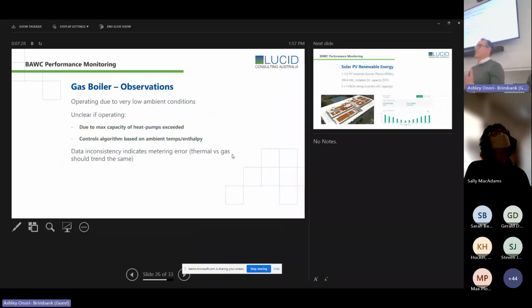So at this stage, we're still working through it. My firm belief is that it's likely a controls algorithm, possibly based on enthalpy or minimum temperatures, where it is kicking in. There's an exercise that we're doing to work through testing what the impact is if we switch that boiler off and see what's happening with the systems.